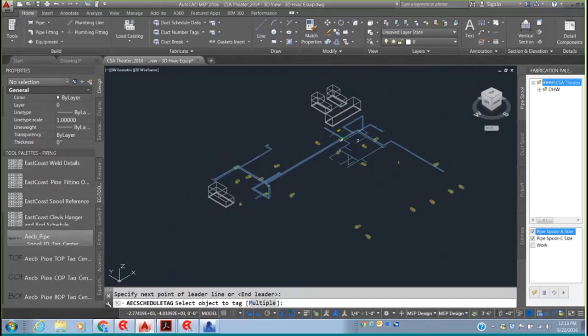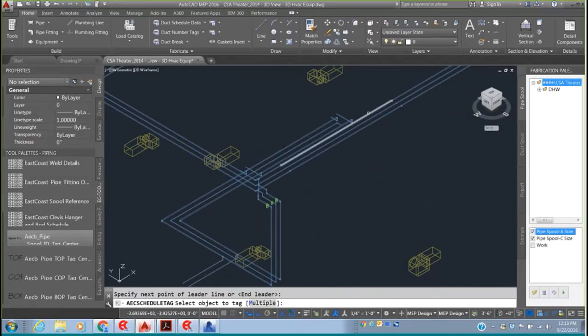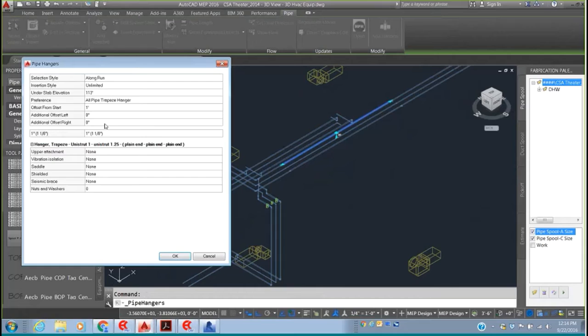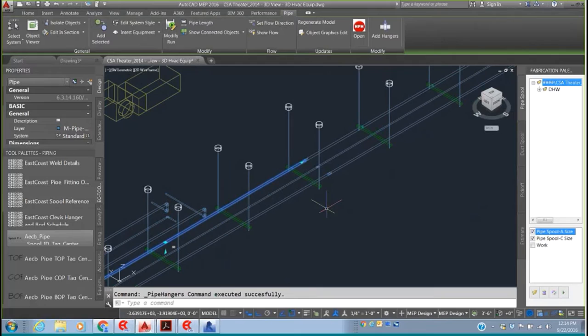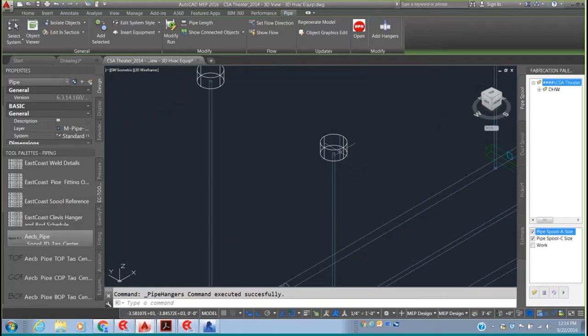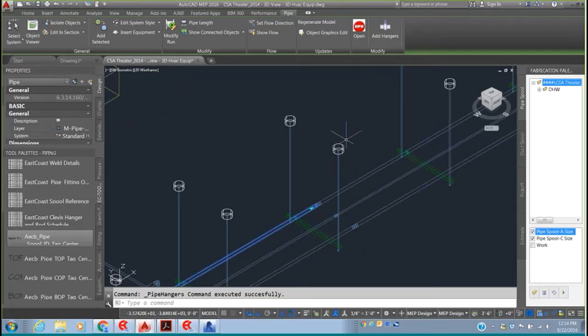I can also add hangers to the model. Clicking on a pipe and selecting Add Hangers opens a dialog — the pipe was at 112 feet, so I want to hang it at 114 feet with an upper attachment using an adjustable beam clamp, offsetting to the left to pick up other pipes. After hitting OK, it runs through and places all the trapeze hangers. It provides cut lengths for the unistrut and rod. The adjustable beam clamp shows a 'circle of influence' — if you can't get your wrench on the clamp, it shows an interference.